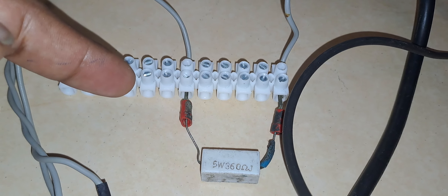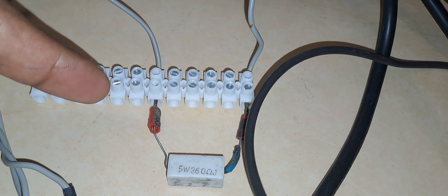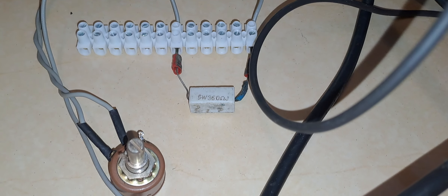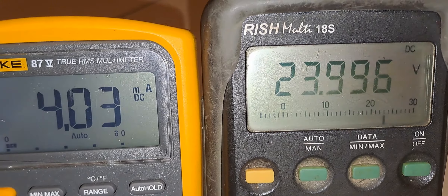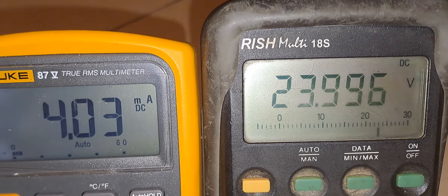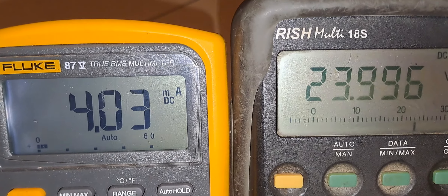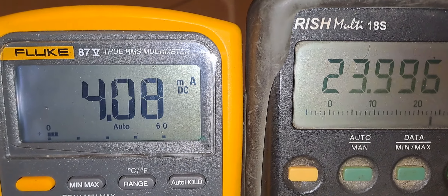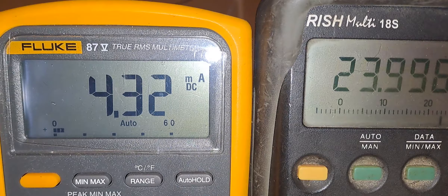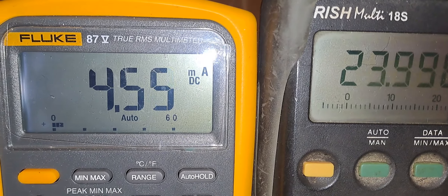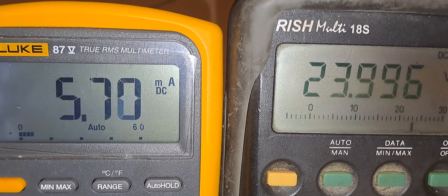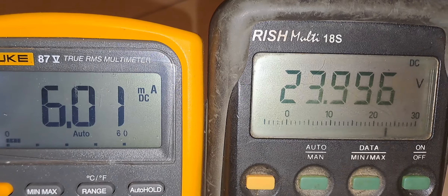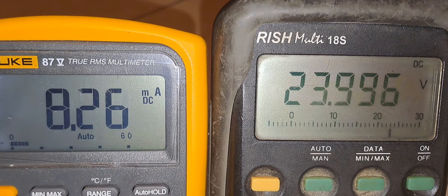The circuit is connected to a 24 volt DC supply. As you can see, the 24 volt DC supply is present and my loop current is 4 milliamps. Now I am going to adjust the current slowly. As you can see I am adjusting the current — you can see 4.24, the current is increasing. The loop current is increasing and the voltage is constant. This current will be fed to an analog input channel.